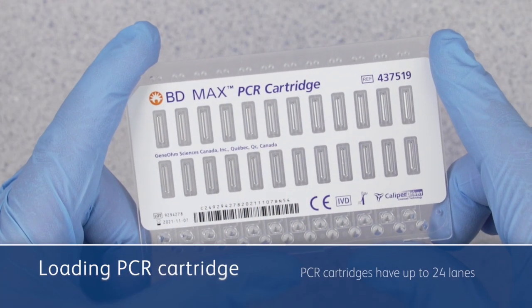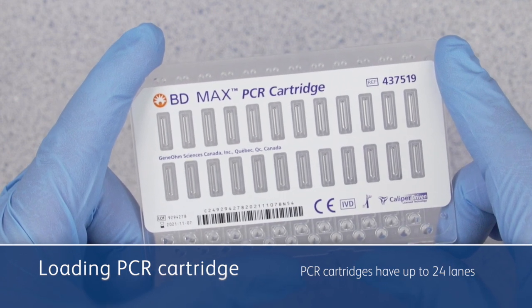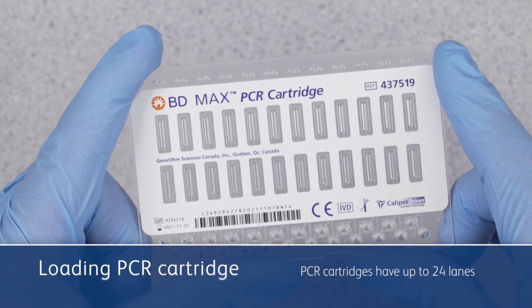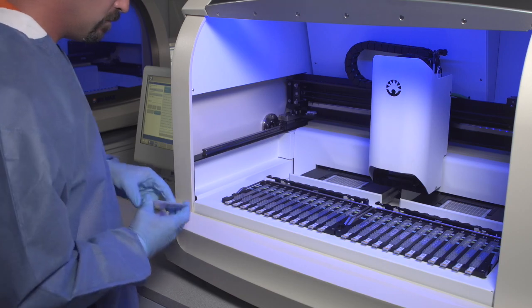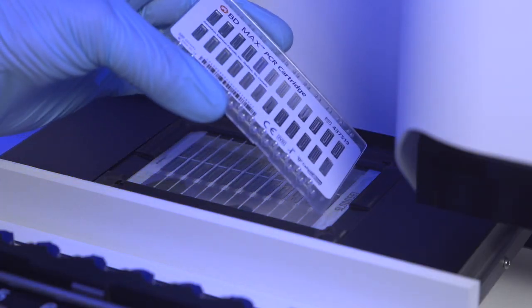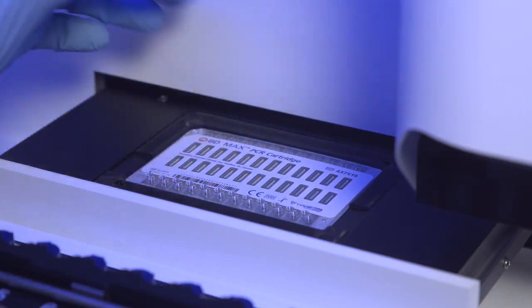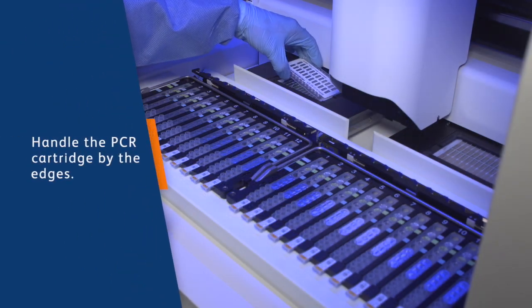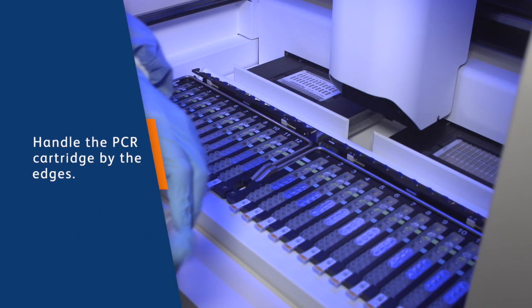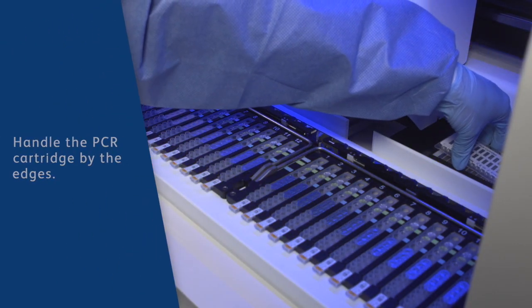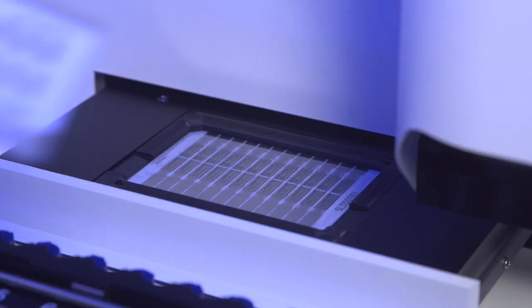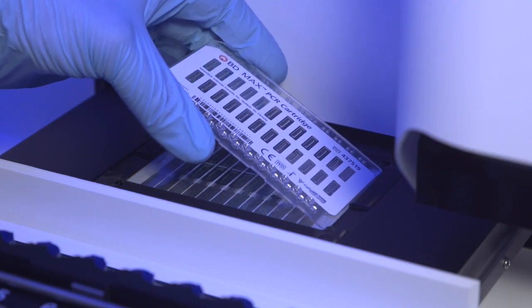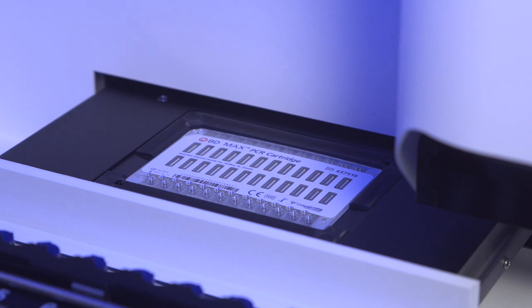BD MAX PCR cartridges can be used multiple times to maximize their usage, up to 24 lanes. Place an unused or partially used BD MAX PCR cartridge into the cartridge drawer. Handle the PCR cartridge only by the edges to ensure that dirt or debris does not interfere with processing. Position the notched edge into the upper left corner of the drawer. Make sure the PCR cartridge is positioned correctly and fits snugly on the drawer.